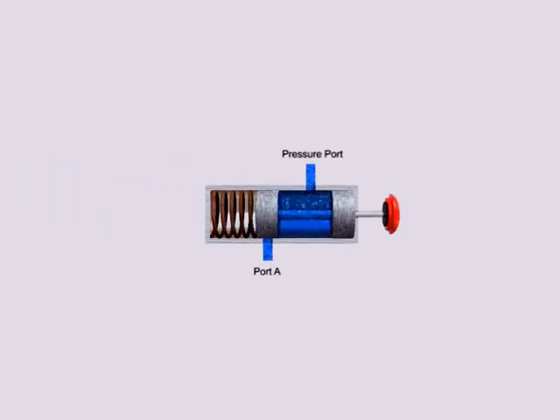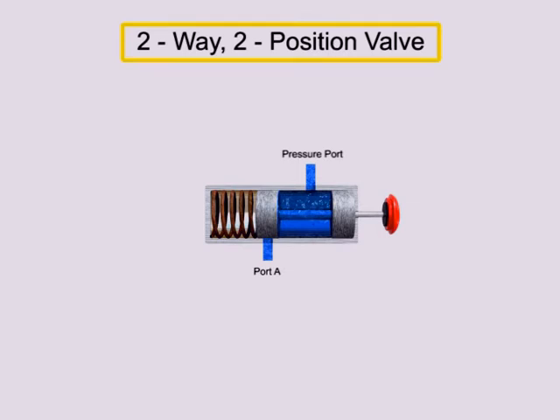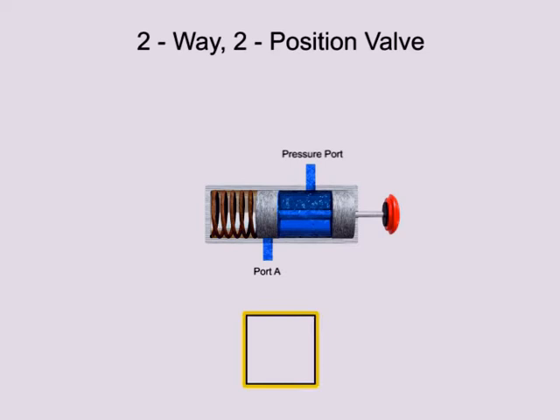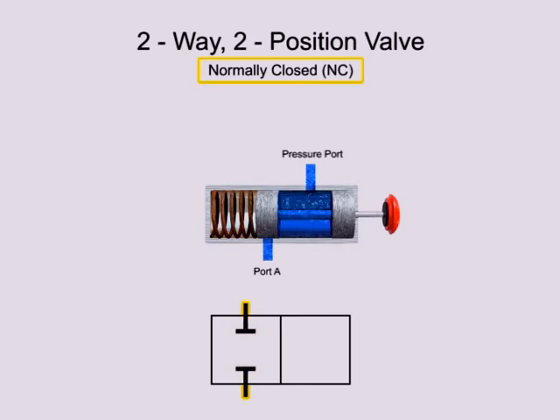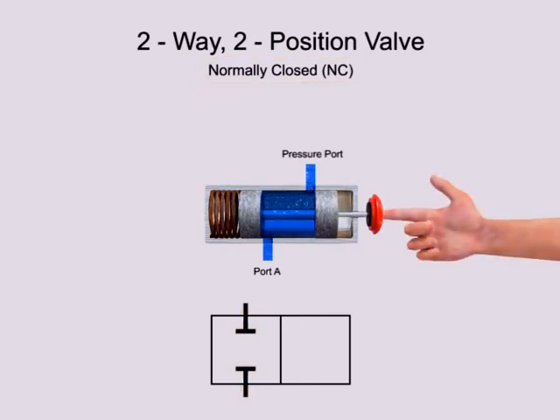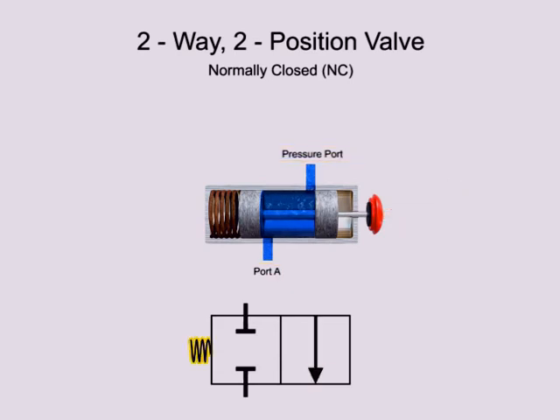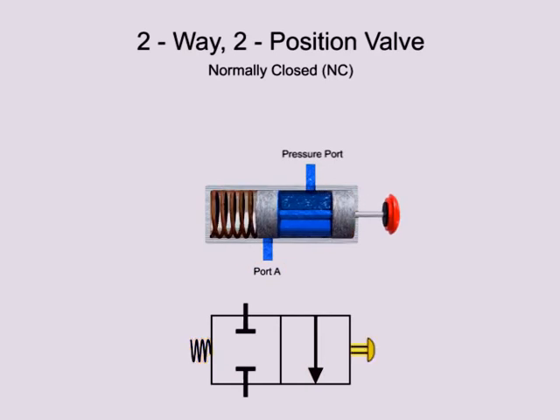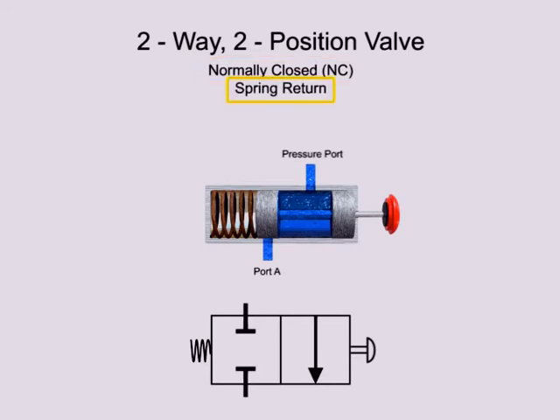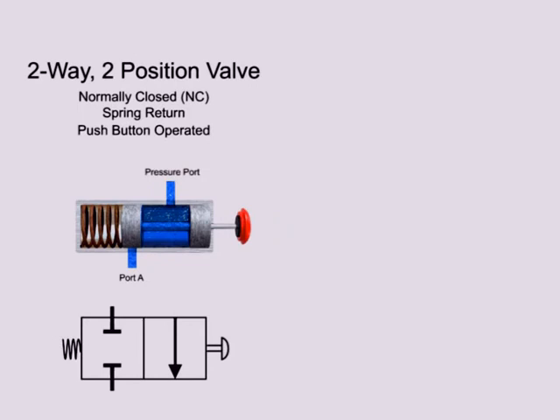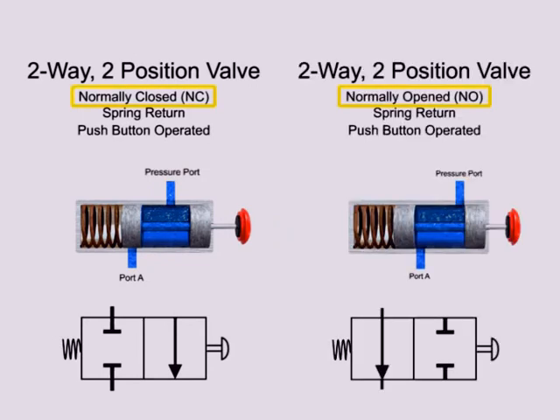Here is a similar valve to the one previously shown. It has two ports and two positions, so it is also a two-way, two-position valve. In the normal non-actuated position, both ports are blocked. Therefore, it is a normally closed valve. When the valve is actuated, fluid is allowed to flow from the pressure port to port A. A spring returns the valve to its normally closed position, and a push button actuates it to the open position. Therefore, this valve is a two-way, two-position, normally closed, spring return, push button operated valve. While it is similar to the previous example, the differences in the normal position make it a distinctly different valve.